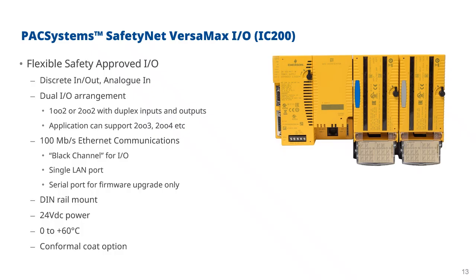So if any one input comes on or any one input goes off, then you trip the safety function. Or sometimes you might have to be monitoring both inputs. So you might say if 2 inputs come on or 2 inputs go off, then you perform the safety function. Same with the outputs. Again, you can either decide when one output turns on or one output turns off, then you trip the safety function, or maybe both outputs have to turn off. And again, that would depend on what your functional safety assessment says and what the application requires.